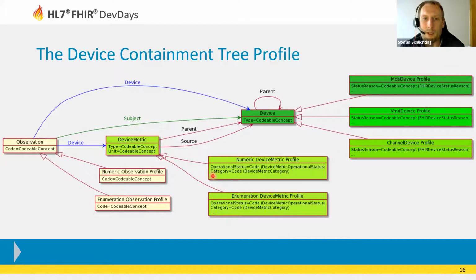There will also be something for real-time sample arrays or sample arrays to represent waveforms, and here you can also see something like an operational status or category. The category, for example, would indicate if we have a ventilation pressure represented by this device metric, and this could either be a measured pressure or the setting applied by the ventilator, which is reflected in the category.